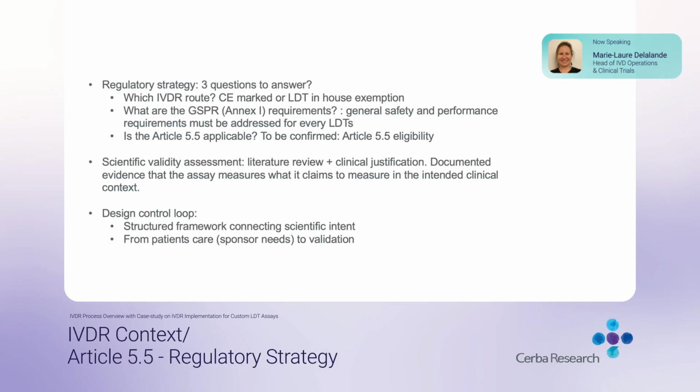Before we run a single experiment, we need to answer 3 questions. First, the route. Here, under Article 5.5 exemption, as Lorella mentioned previously. Second one, what are the GSPR requirements? The GSPR requirements in Annex 1 of the IVDR. Every LDT must address this GSPR. They define what good enough looks like from a regulatory standpoint.